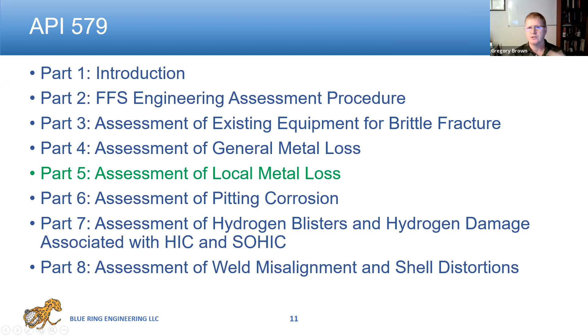Part 8 is about misalignments. A pressure vessel should be round, which gives a nice even hoop stress field. If it's not, you get higher bending stress, which can actually lead to failure, often due to fatigue. The guidelines in Part 8 tell you how to assess out-of-roundness and weld peaking situations.